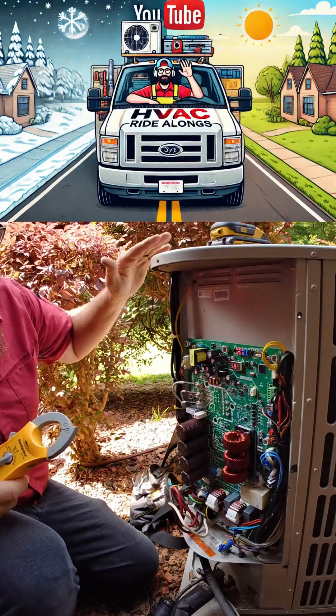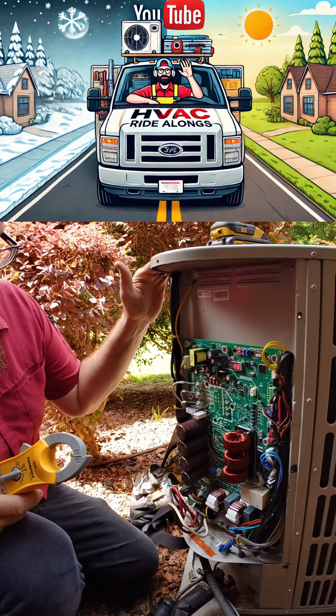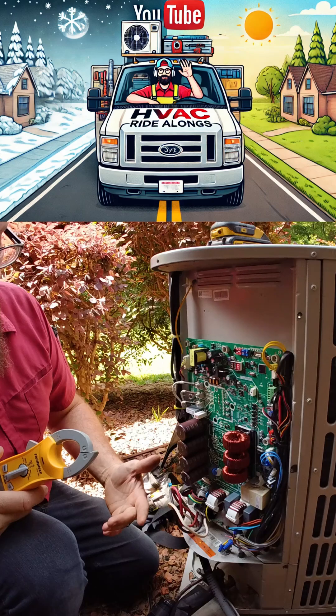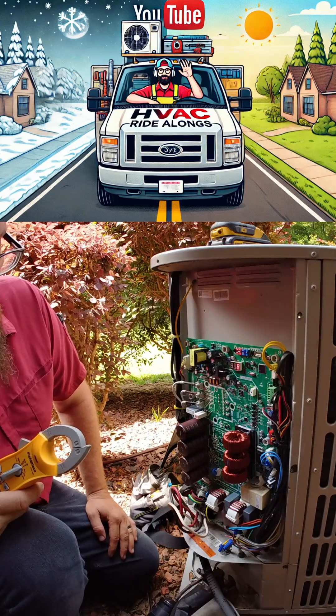So how you actually troubleshoot pressure transducers — these units are doing much the same as our gauges do. It's watching the ambient outdoor temperature, the coil temperature, temperatures on our lines, and the pressure transducers are actually watching the refrigerant pressure.